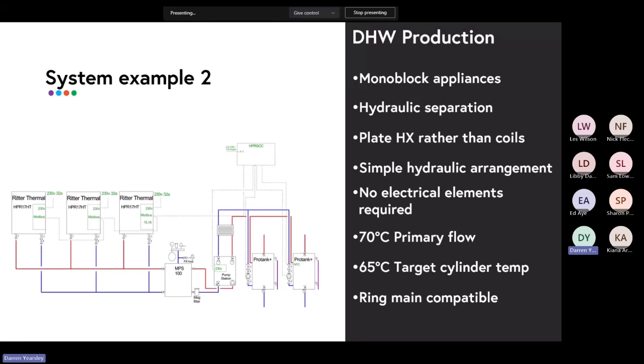And I'm not a particular fan of that, because sometimes you'll have water entering that port, and other times under recovery you'll have water exiting that port, and it's a bit odd to have water traveling in both directions through those ports. So wherever possible, I like to have dedicated recovery ports so we can completely hydraulically separate. So very simple hydraulically. The pump comes on, sucks water out of the bottom of the tank, drives it through the plate heat exchanger, and then drops it back in again.